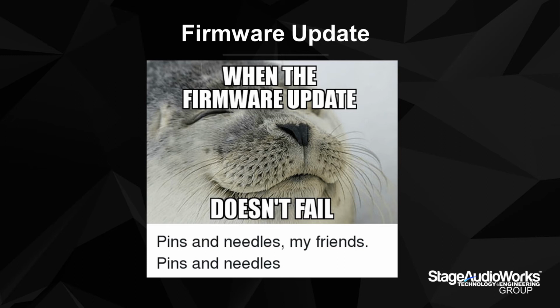The other question is, do you really need to do the firmware update? Just because a firmware update is released doesn't mean you need to install it. The important thing is to read through the release notes and see what features are added. If you don't require those new features, and the equipment is mission critical and has been running stable for a year, I won't touch it. If it's not broken, don't fix it. I would only do a firmware update if I actually require that new version.